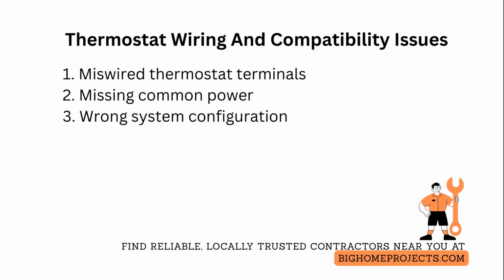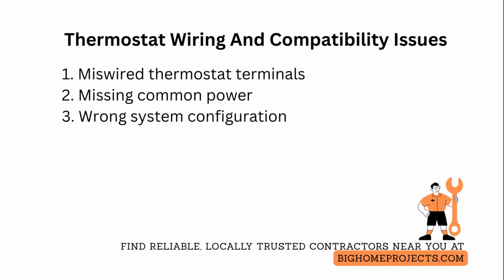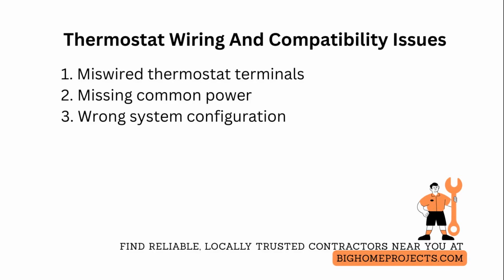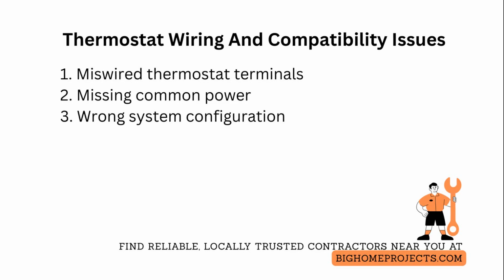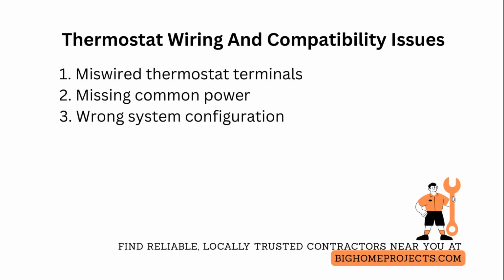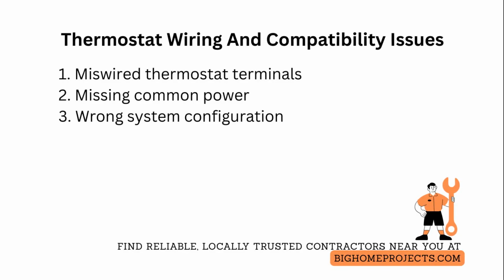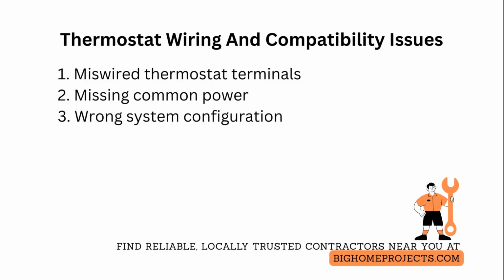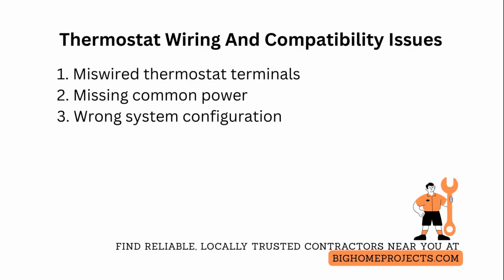One of the common thermostat installation mistakes is miswired terminals causing only heat or only cool to work. Fix by mapping each conductor from thermostat to equipment, using a continuity tester and adding the correct jumper between the two red terminals if the system needs it. Another frequent issue is missing common power, leading to intermittent operation. Resolve by running a dedicated common conductor or installing a manufacturer-approved power extender or a new thermostat with internal transformer support.